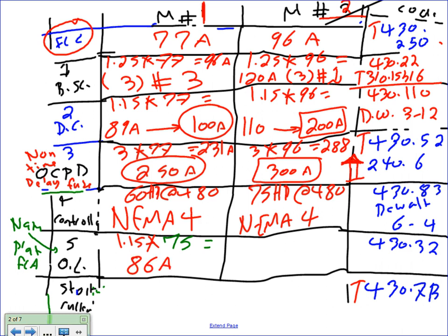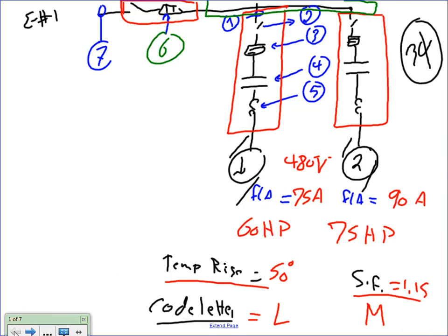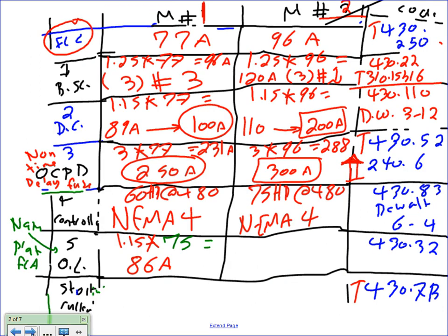The second motor, guys, has a service factor of 1.15. Where did the 75 come from? For the overload, we always multiply the full load amp on the nameplate. Please write yourself a note: the full load amp on the nameplate is always used for overload. Overload only. Cool? So here's my 75. The service factor of motor number 2 is 1.15, so the multiplier is 1.25 multiplied by this. Motor number 2 is 90 amp, and from here it equals 113 amp. How many? 113 amp.